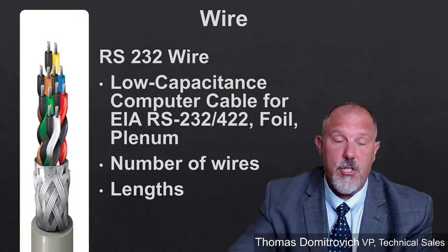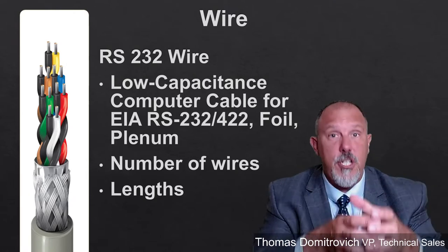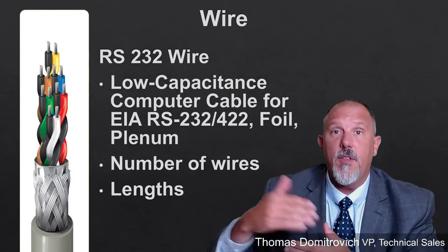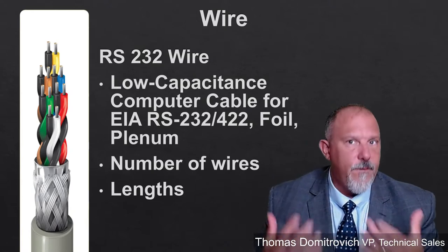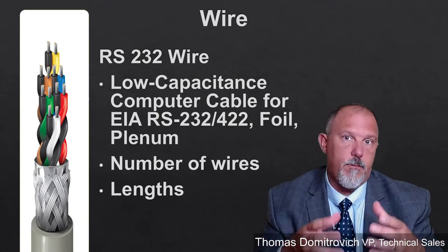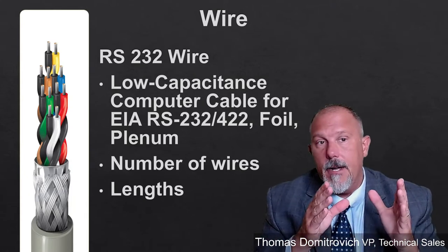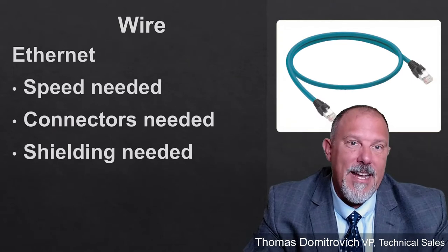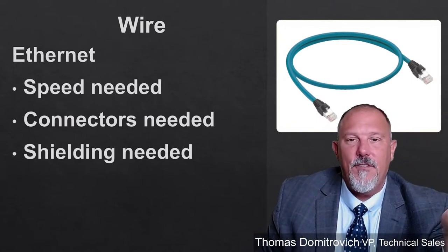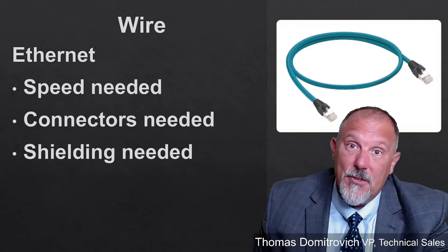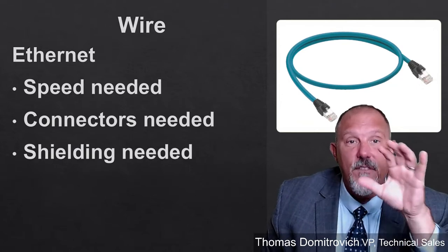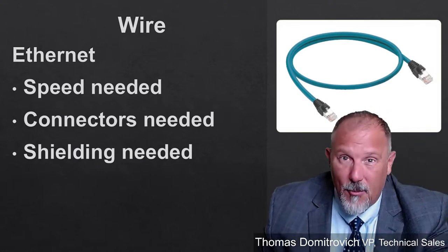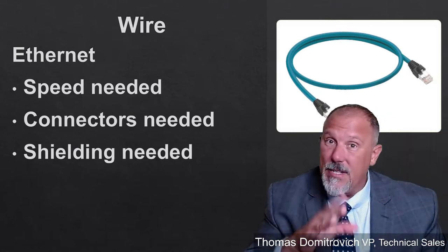It's still a technology that is used in that world, and you've got to think about the physical wires, the shielding, and the insulation rating, or voltage rating. If you're running these communication lines in with or around other power cables, you've got to have the right voltage ratings for protection of those conductors. You also need the proper shielding, the right colors, and the right number of conductors. Then you have your Ethernet wires, which have RJ45 connectors at the end, and your telephone wires, RJ11s, I believe. Your physical layer is important to understand: the wires you're using, the voltage ratings of those wires, where you can and cannot route them, and the shielding and bonding of those.